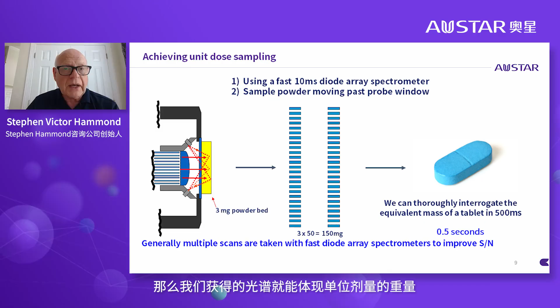So I just want to show you some evidence of the poor sampling that you get with these fibre optic probes if the sample is stationary. On the left-hand side of this plot, you can see we scanned a powder, actually we scanned it 10 times in the dish, and we moved the powder between each scan. And then we tried to build a calibration from the powders of different strength. In fact, there are 7 different strength powders here from those single scans of a stationary powder.